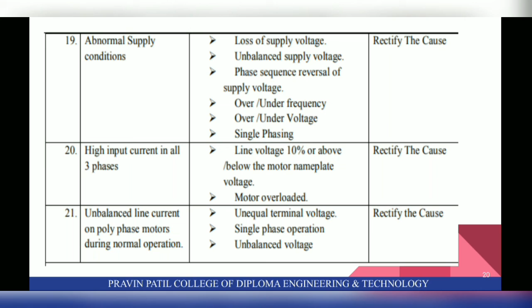Next trouble is high input current in all three phases. Causes are line voltage 10% above or below the motor nameplate voltage, or motor overloaded, and suggested corrections are rectify the cause. Next trouble is unbalanced line current on polyphase motors during normal operation. Causes are unequal terminal voltage, single phase operation, unbalanced voltage, and suggested corrections are rectify the cause.